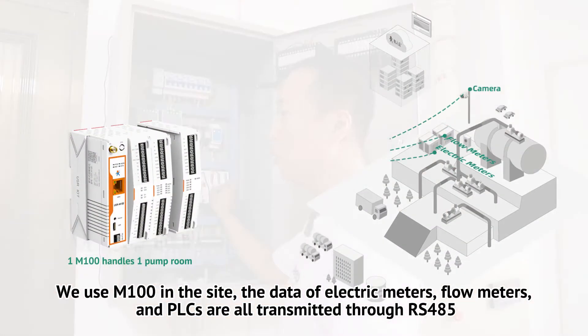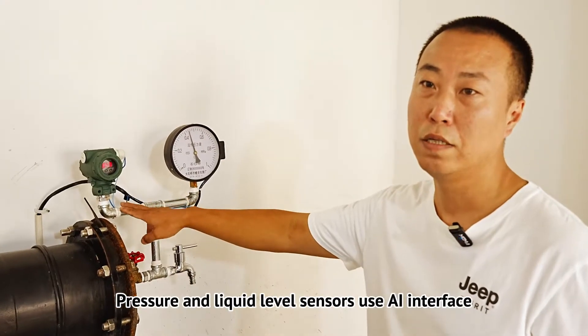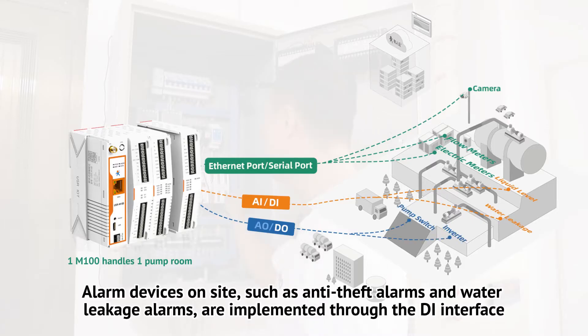The data of electric meters, flow meters, and PLCs are all transmitted through RS-485. Pressure and liquid level sensors use the AI interface. Alarm devices on site, such as anti-theft alarms and water leakage alarms, are implemented through the DI interface.